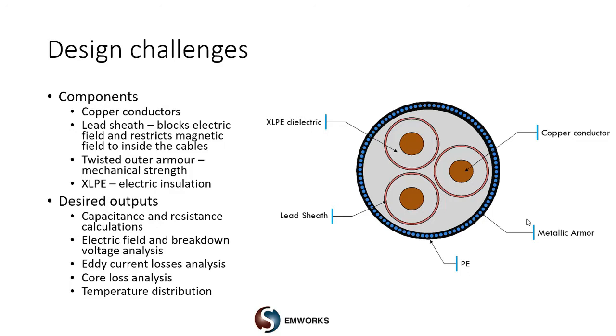Before looking at design challenges, let us take a look at the structure of a subsea power cable. Here on the right I have a cross-section of one such commonly used design. You can see the conductors that carry electricity, covered with a lead sheath that blocks the electric field from leaving. There is also a twisted outer armor providing mechanical strength. All of these are packaged inside XLPE, which acts as an excellent electrical insulator.